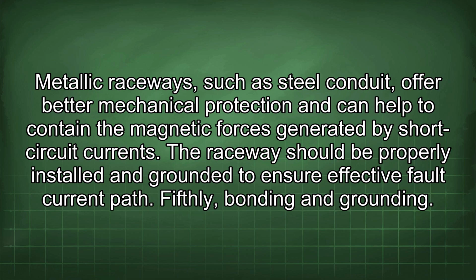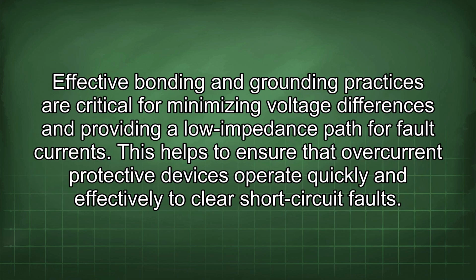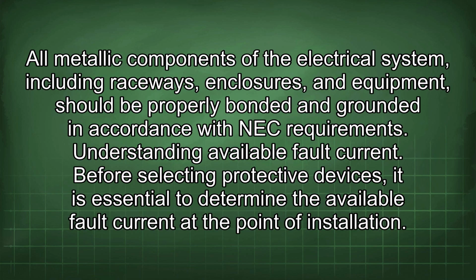Fifthly, bonding and grounding. Effective bonding and grounding practices are critical for minimizing voltage differences and providing a low impedance path for fault currents. This helps to ensure that overcurrent protective devices operate quickly and effectively to clear short-circuit faults. All metallic components of the electrical system, including raceways, enclosures, and equipment, should be properly bonded and grounded in accordance with NEC requirements.